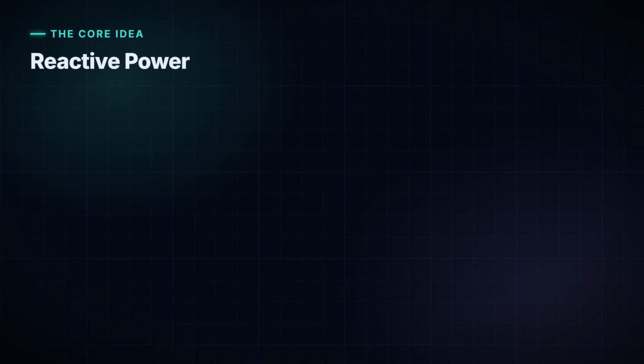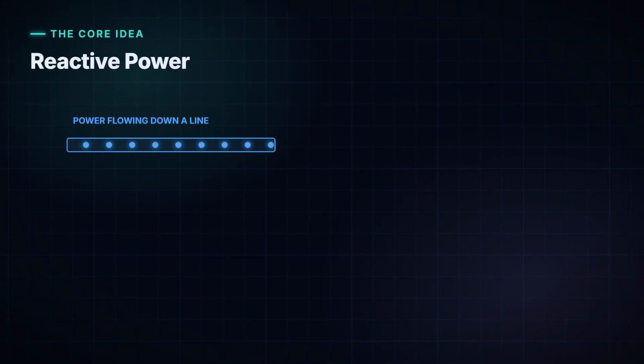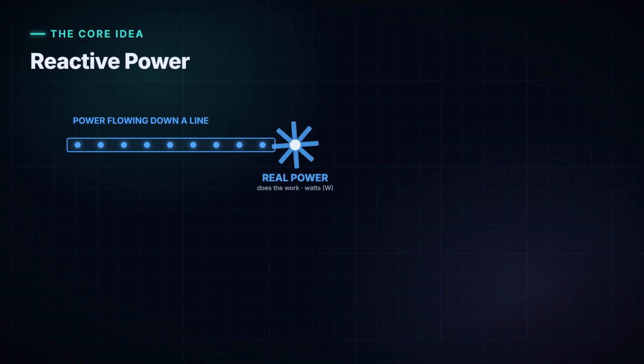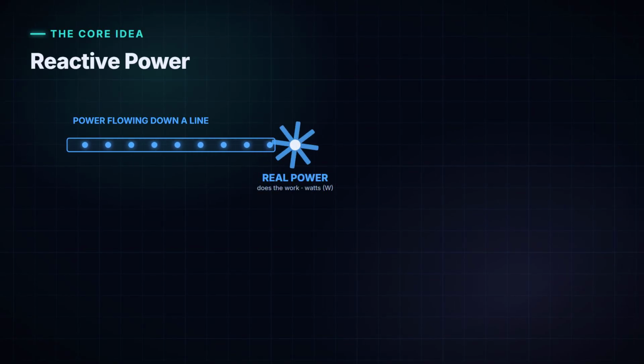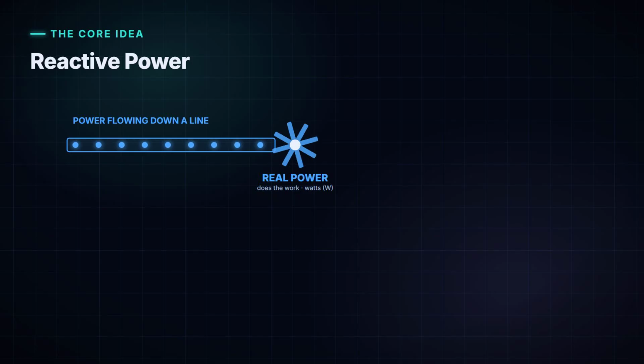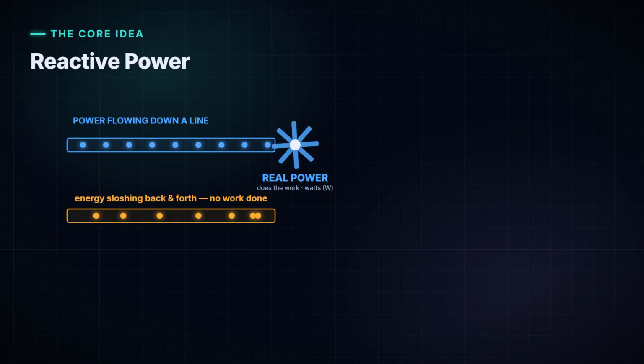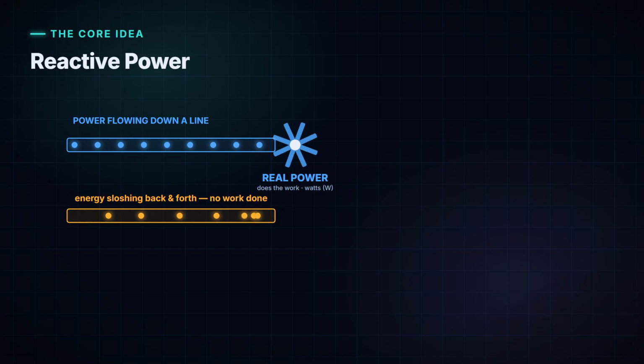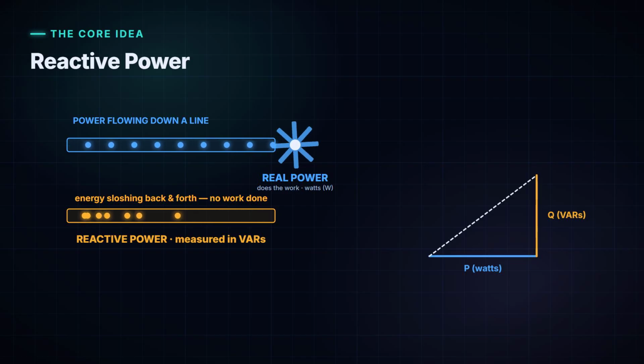Before we can understand the device, we need to understand the problem it solves, and that means talking about reactive power. Here's the cleanest way to picture it. Think of the power flowing through a line as water being pushed through a pipe. The water that actually turns a wheel and does useful work, that's real power, measured in watts. But the grid is full of motors, transformers, and long lines, and these store energy in magnetic and electric fields, then give it back every single cycle. That sloshing back and forth energy doesn't do useful work, but it still has to flow through the wires. We call it reactive power, and we measure it in VARs.